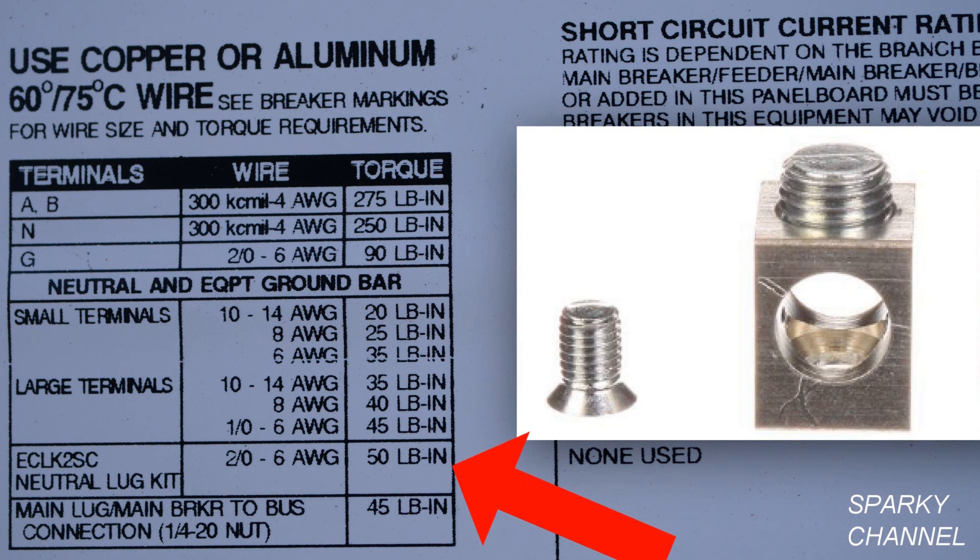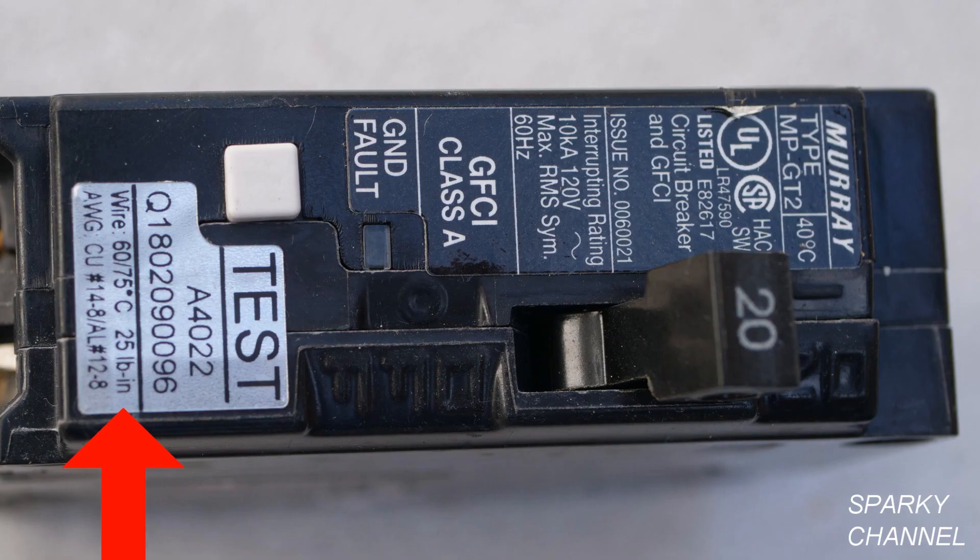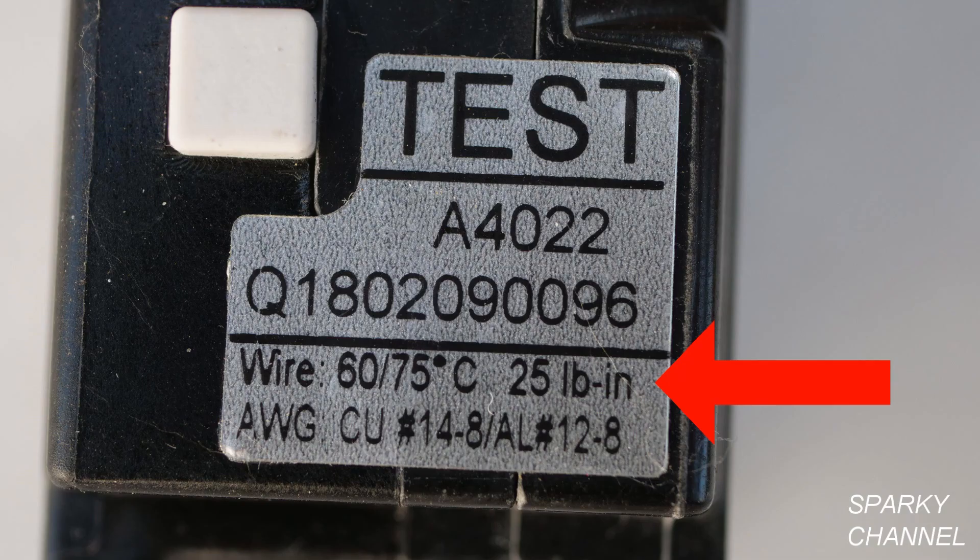The neutral lug kit seen on the right would be torqued at 50 pound inches. The quarter-inch nuts that the red arrows are pointing to are to be torqued down at 45 pound inches. The torque rating for breakers will be found right on the breaker — this one is 25 pound inches.